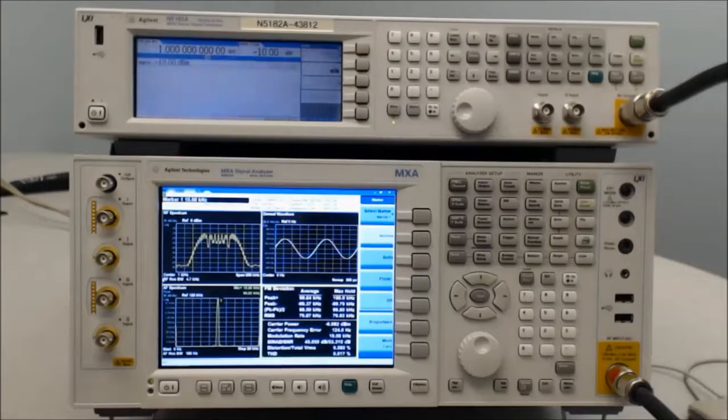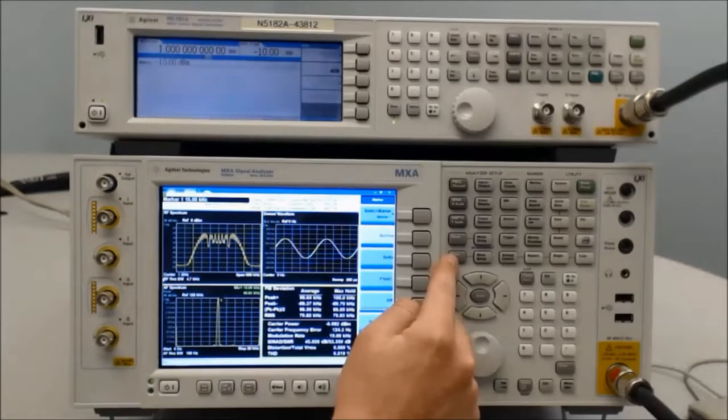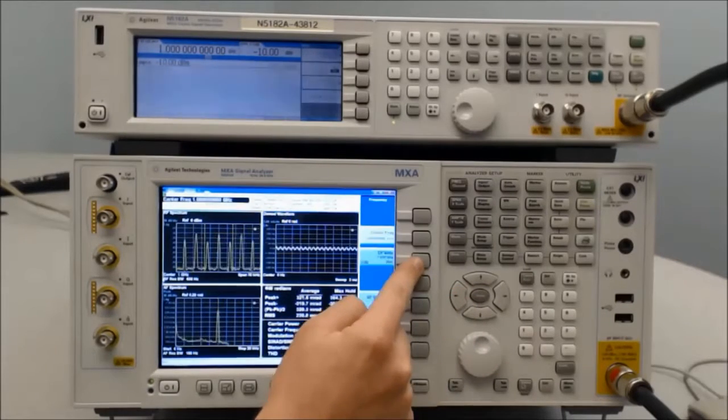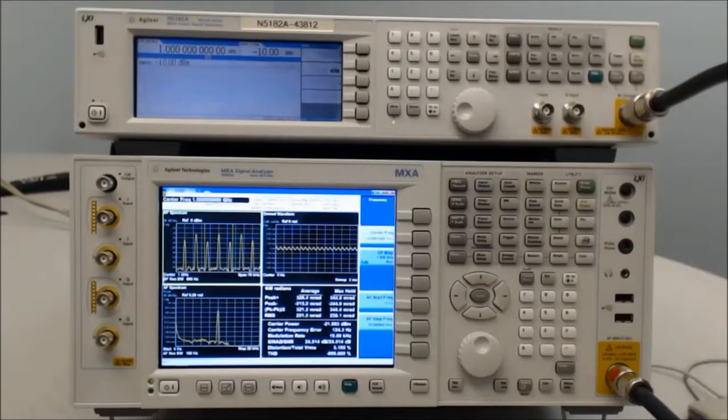To measure PM instead of FM, we want to go to the measurement setup and measure PM. Repeat the same steps I just listed and you will be able to measure PM deviation and the PM rate.